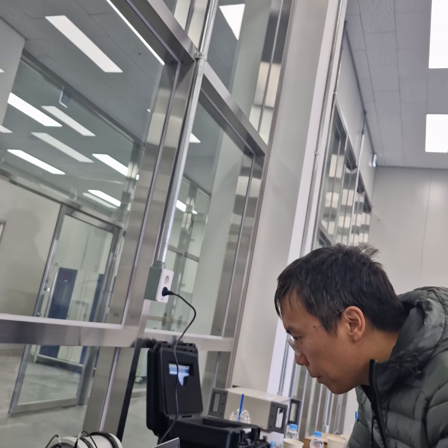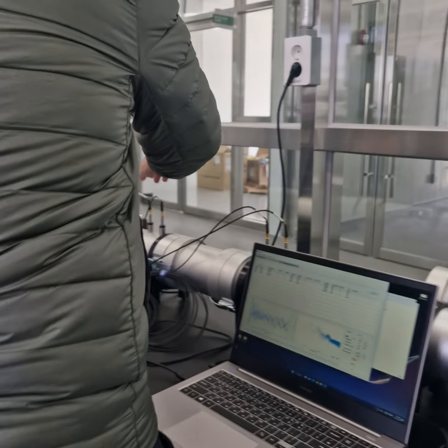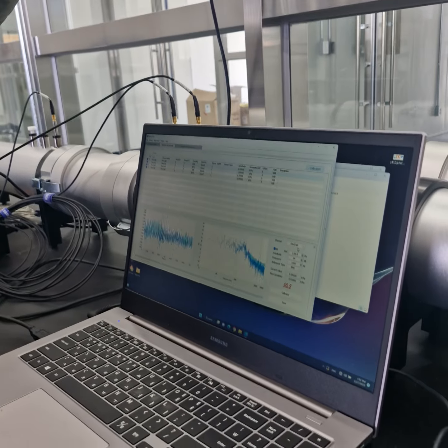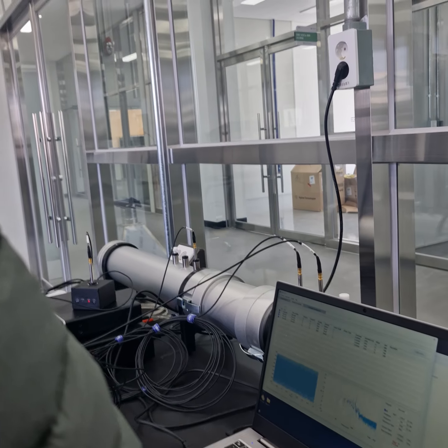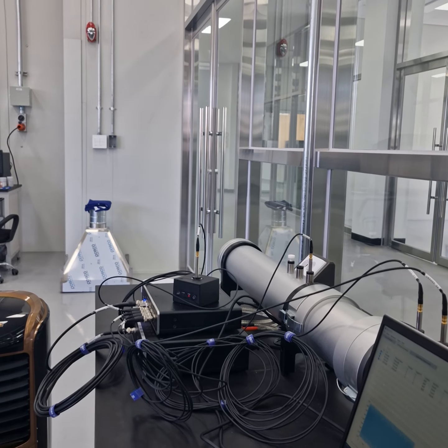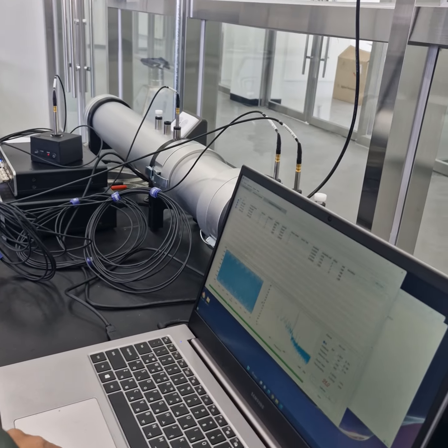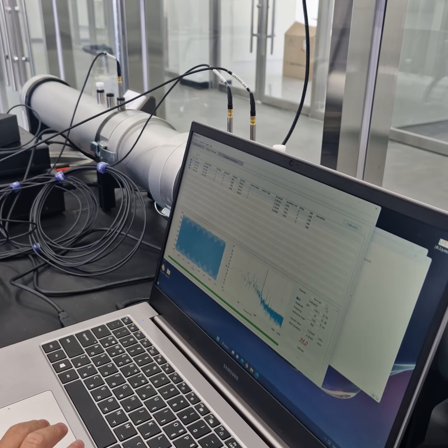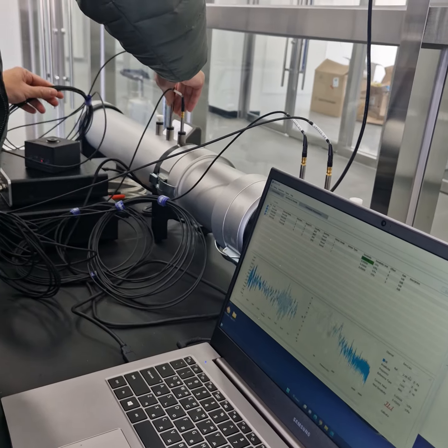Same thing. We click on the calibration, and then we take out channel 1, turn on the calibrator, plug it in, and then you see the peak here at 1000 hertz. Then you click calibrate. And then save. And then we switch to channel 2. And then we change it.